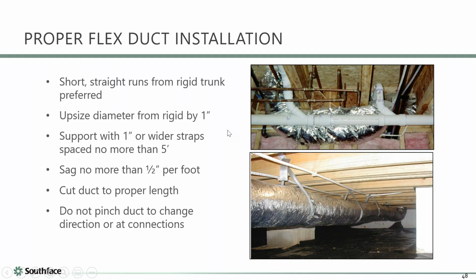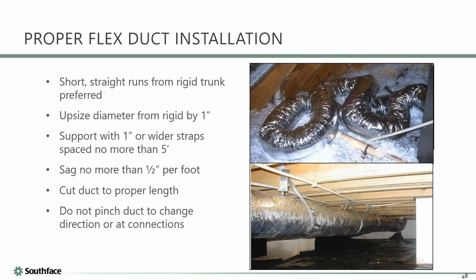A good rule of thumb, and this is an okay rule of thumb, is to upsize the diameter. If you need a 5-inch metal duct, use a 6-inch flex duct. Going up one inch in diameter will help alleviate some of those problems. It comes in a box that's 25 feet long. If you're trying to connect to a fitting that's about 8 feet away and use all 25 feet, not only is that 25 feet of resistance, but if you turn air 90 degrees with a typical elbow, it adds like 15 to 25 feet of equivalent resistance. So this duct is now several hundred feet long effectively.